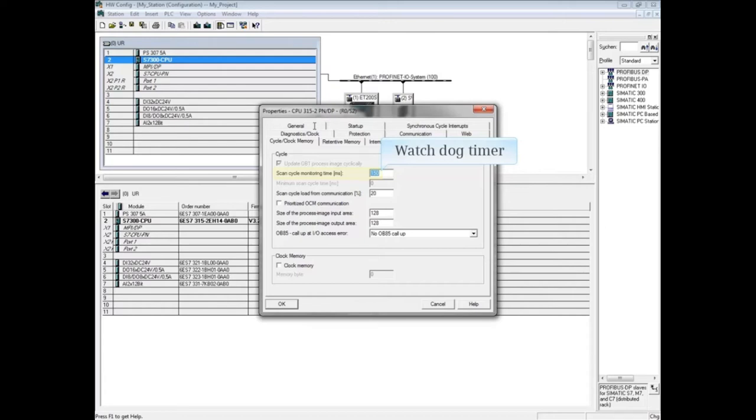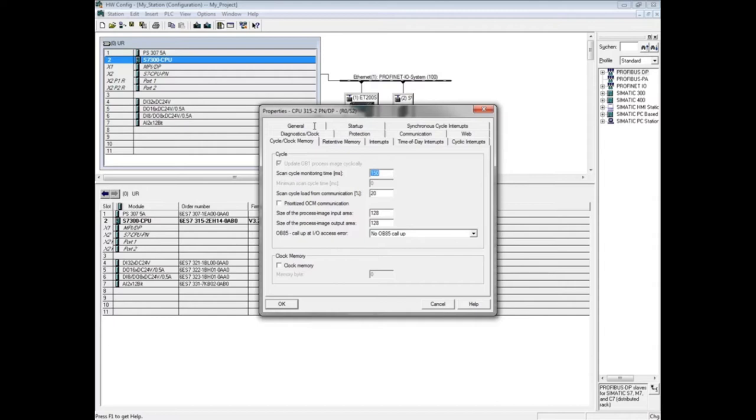If the scan time is exceeded, OB80 is called if it has been downloaded to the CPU, and the watchdog time will be temporarily expanded. If OB80 is not in the CPU, the mode will be switched to stop. You can reduce this number or expand it up to 6,000 milliseconds.